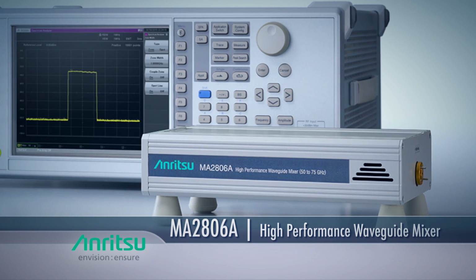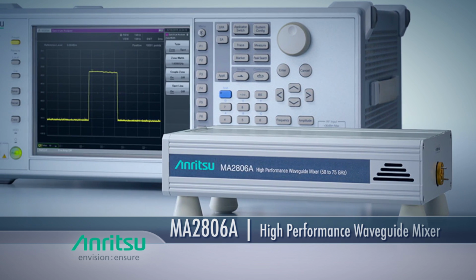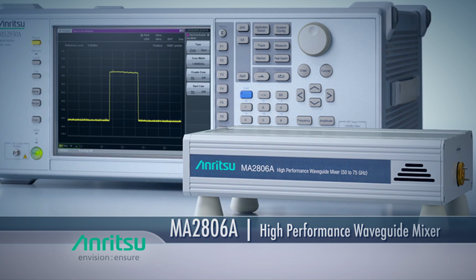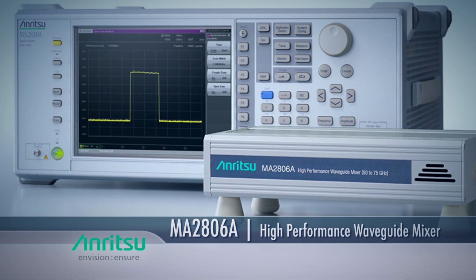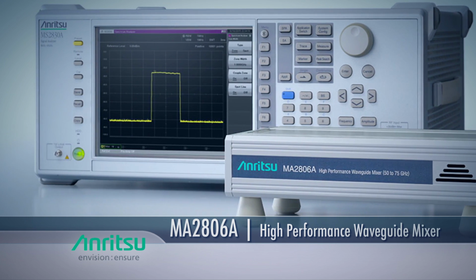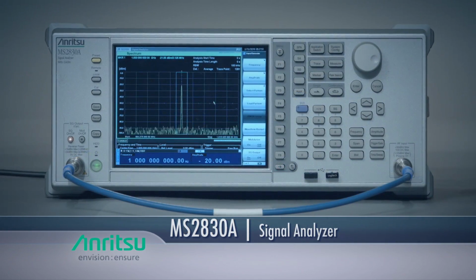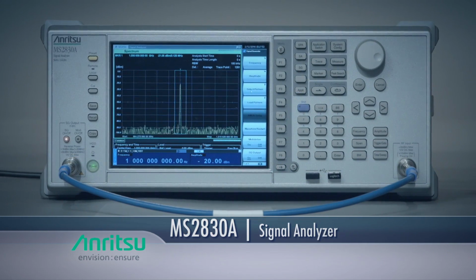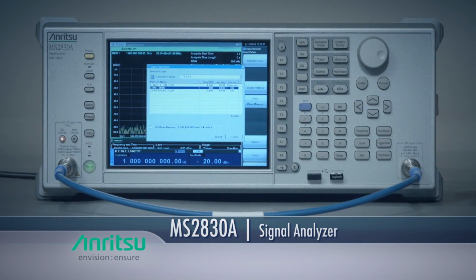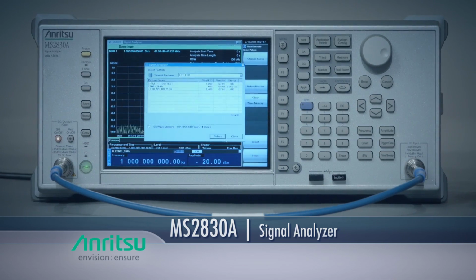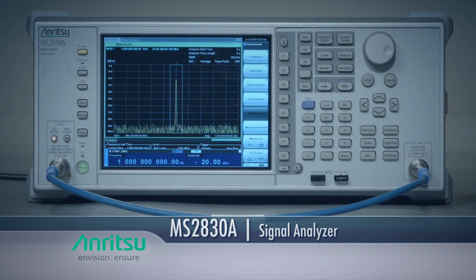It replaces legacy methods that use a down converter that requires a separate mixer, spectrum analyzer, expensive microwave signal generator, multiplier, and other equipment. The MS2830A with the MA2806A can measure extremely weak signals at V-band frequencies that are typically missed by conventional measurement systems.